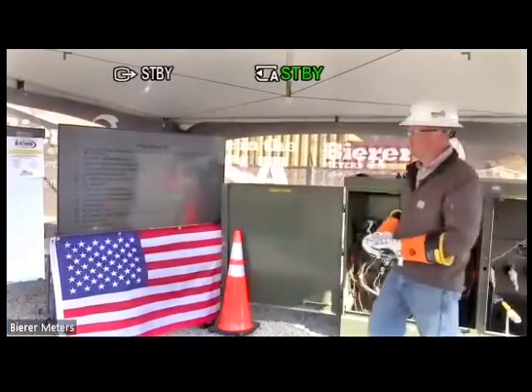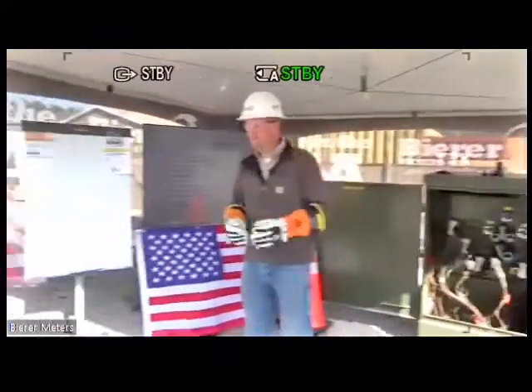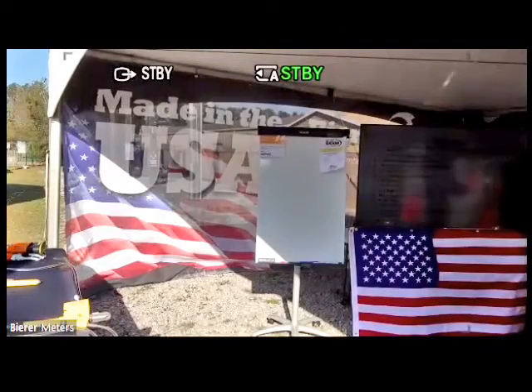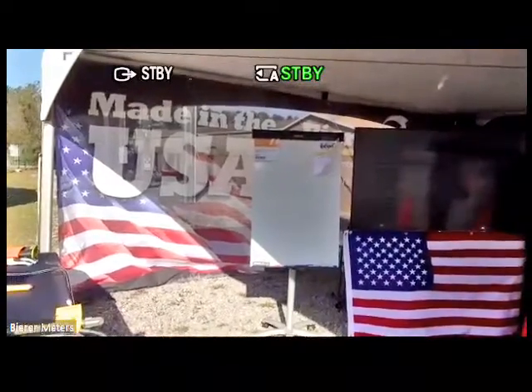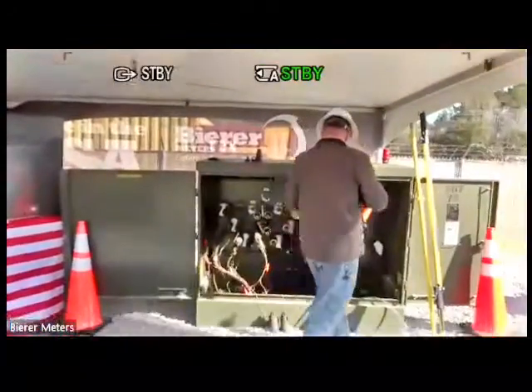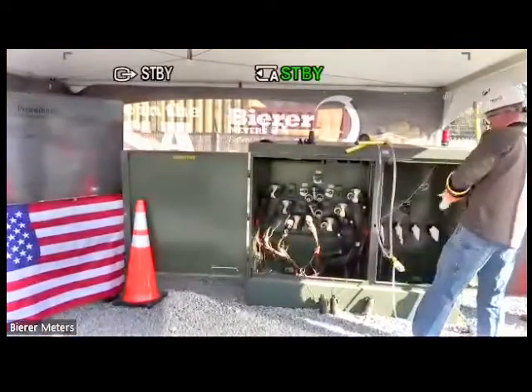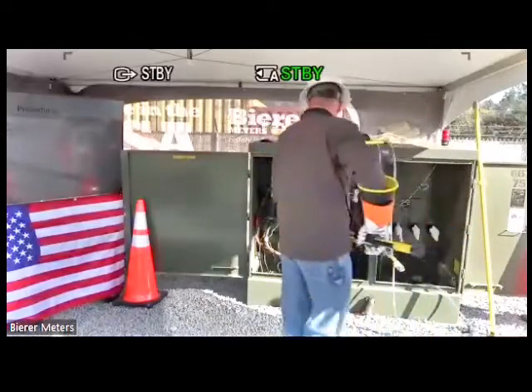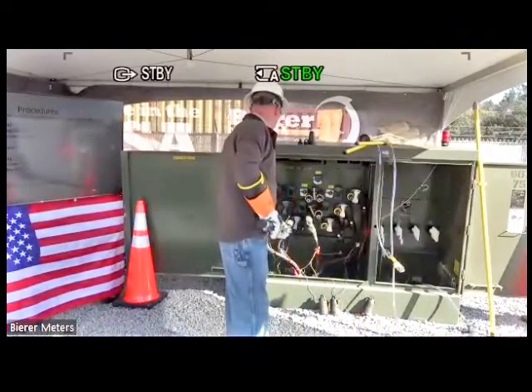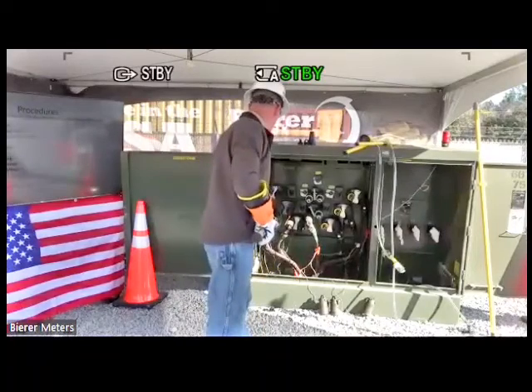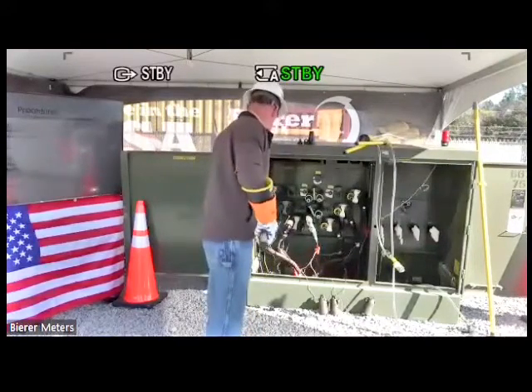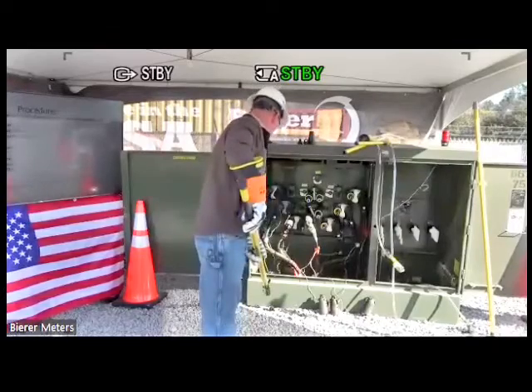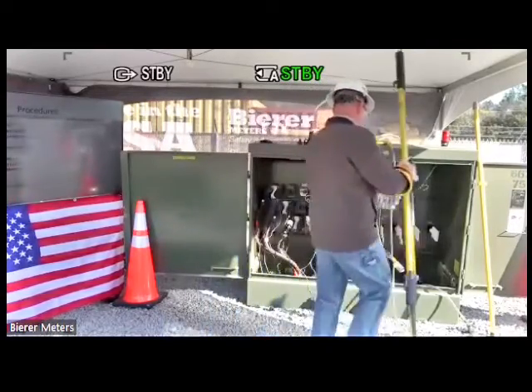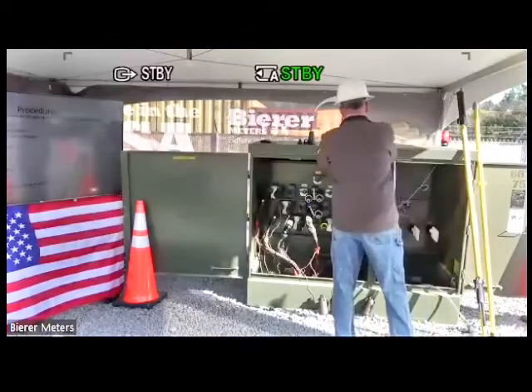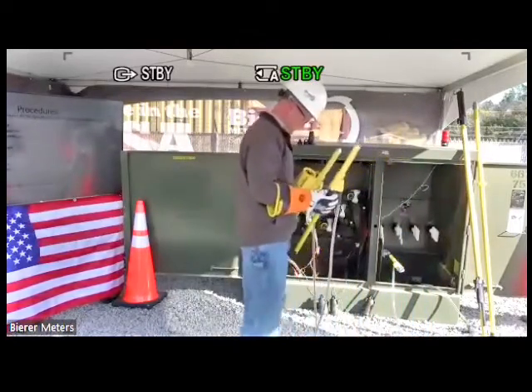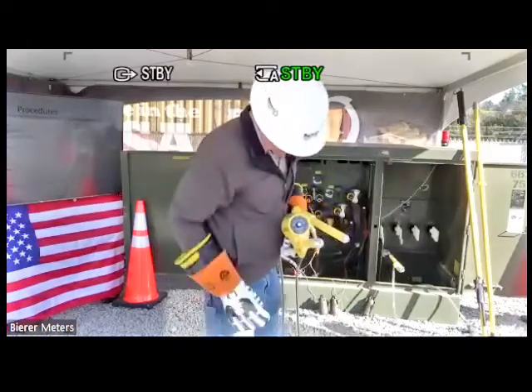All right. So next on the list, capacitive test point phasing. And I'm going to phase across these capacitive test points. As I mentioned a moment ago, whenever you're phasing capacitive test points, you have to make sure the capacitive test points are actually good because they have been known to fail. Like I said, we actually have one in our yard that's already failed on us, and it's just a few years old. And you can just imagine in the field, 20, 30 years or however long, they could fail pretty easily.